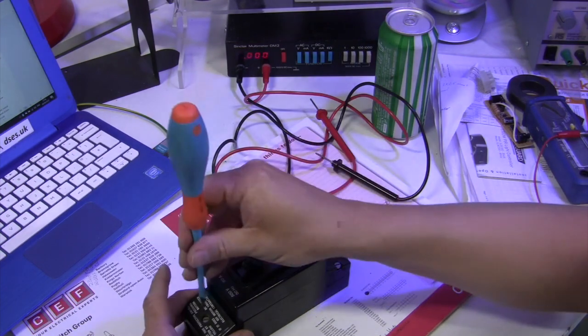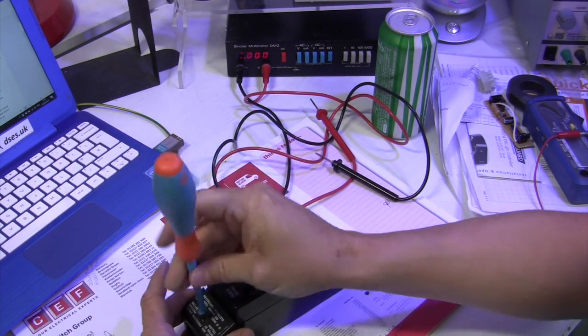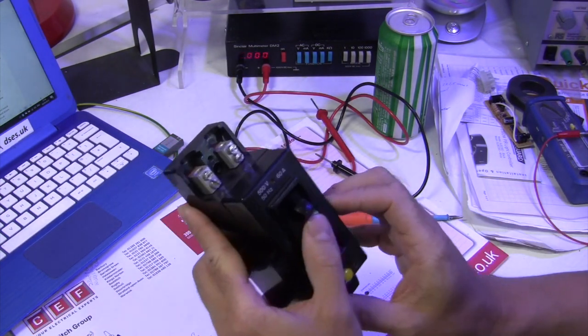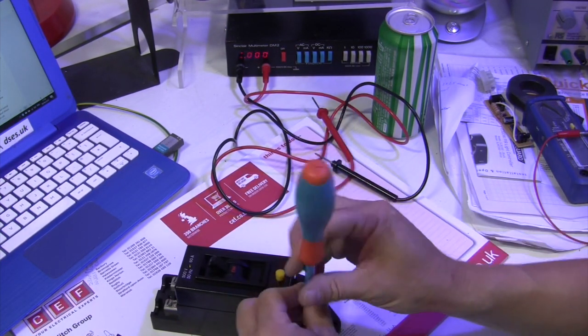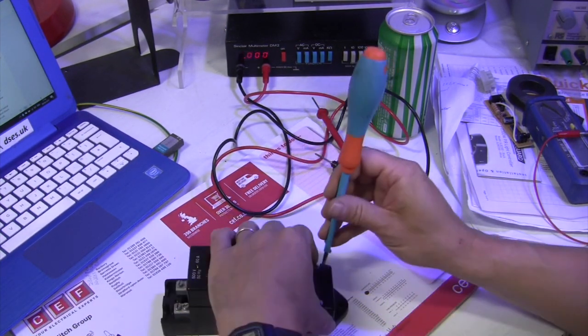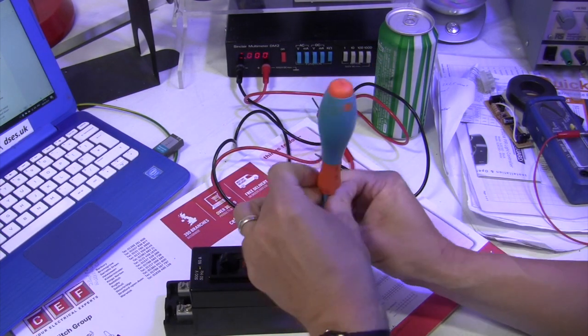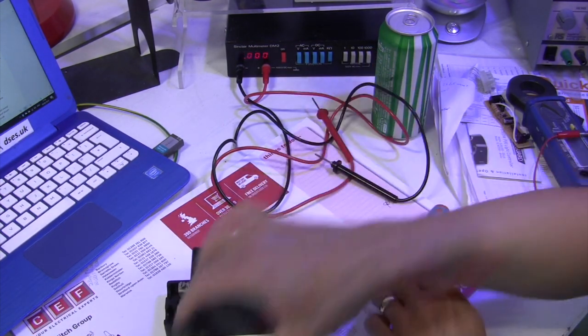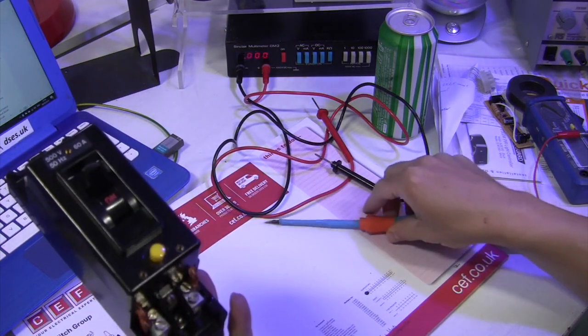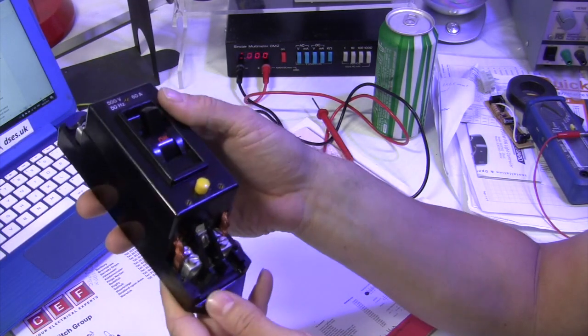And if I remove the covers, you can see the top terminals where the incoming line and neutrals would have once been. There we go there, labelled N and L accordingly. And if I remove the two screws from the bottom cover, we'll see the outgoing terminals, which are labelled, in this case, N and P for neutral and phase. The old terminology of the 14th edition coming out there.